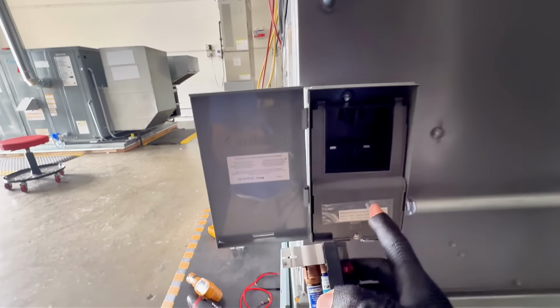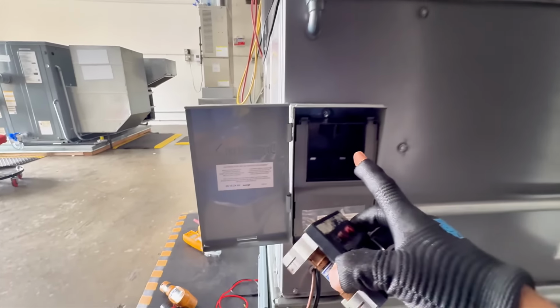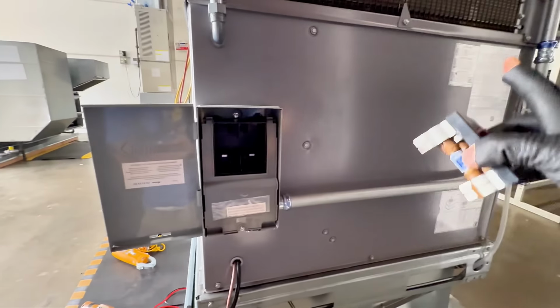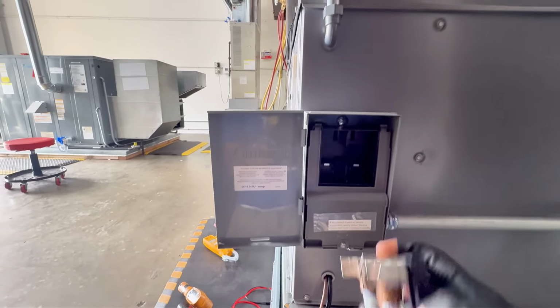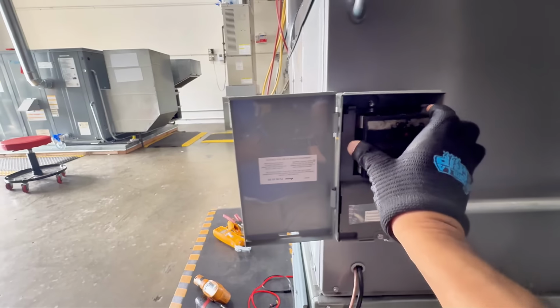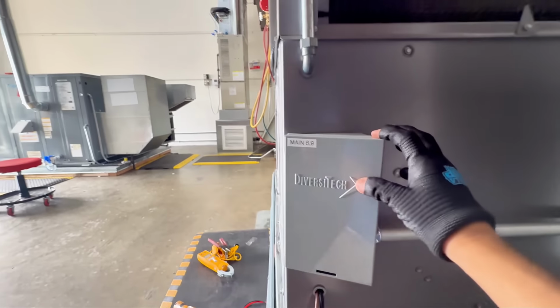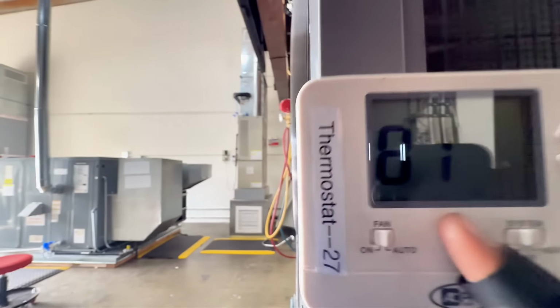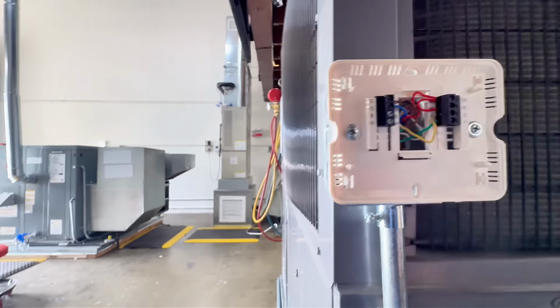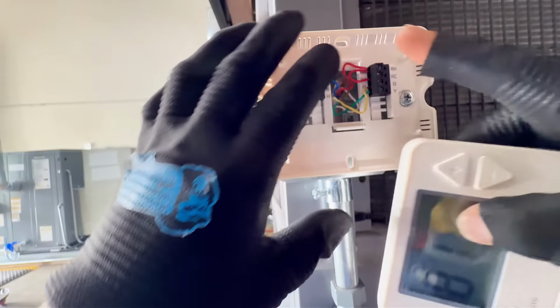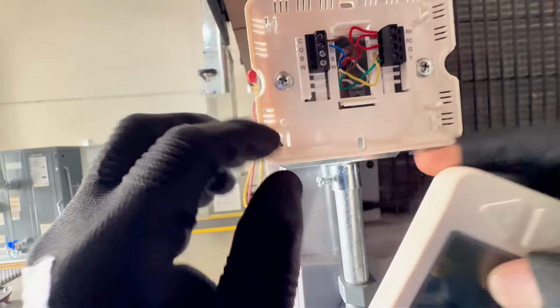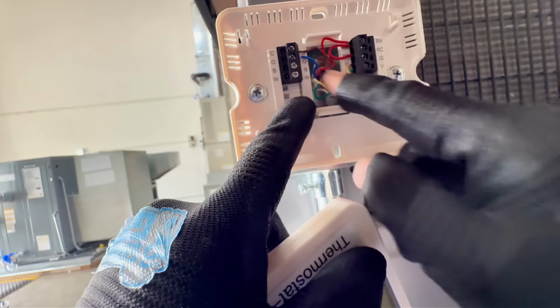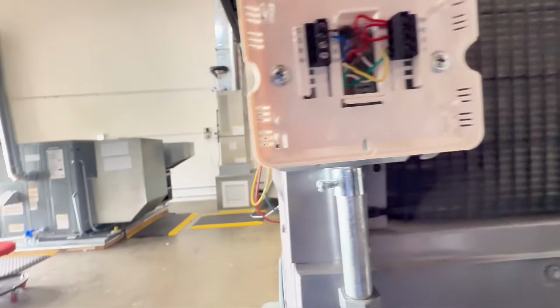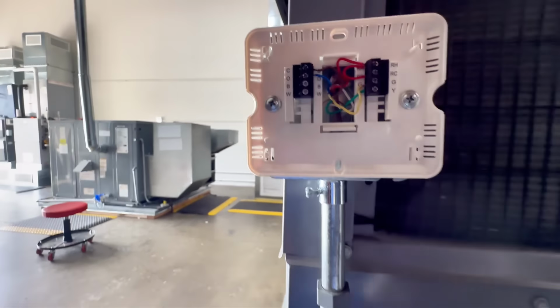I don't necessarily have to open this up and check if there's power. If the breaker is tripped and nothing turns on, then you got to find out why it tripped. Grounded compressor, something that's pulling a lot of amps. But let's just say this is plugged in when you get to the job. And sure enough, I have power, right? So at this point, at least for myself, I would start off with the low voltage with the thermostat. So if it has power, right, it's on, I should be getting 24 volts between common and my red. So we know that we do because it turned on.